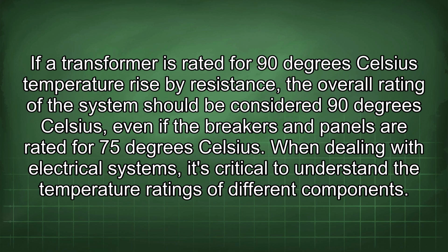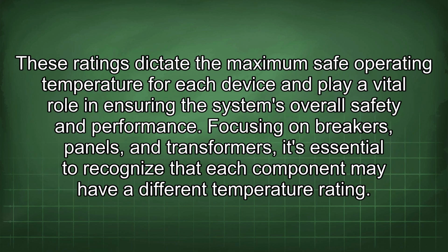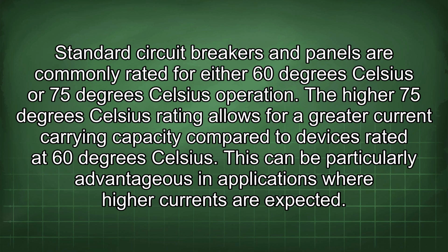When dealing with electrical systems, it's critical to understand the temperature ratings of different components. These ratings dictate the maximum safe operating temperature for each device and play a vital role in ensuring the system's overall safety and performance. Focusing on breakers, panels, and transformers, it's essential to recognize that each component may have a different temperature rating. Standard circuit breakers and panels are commonly rated for either 60 degrees Celsius or 75 degrees Celsius operation. The higher 75 degrees Celsius rating allows for a greater current carrying capacity compared to devices rated at 60 degrees Celsius. This can be particularly advantageous in applications where higher currents are expected.